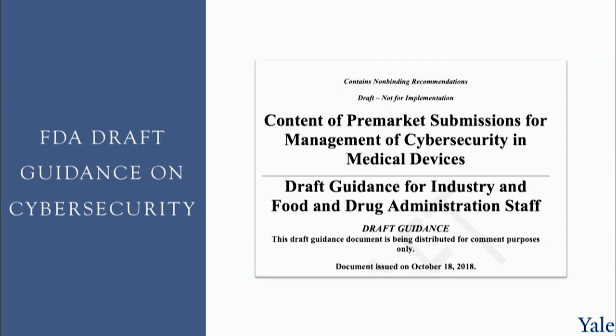So the FDA also has its guidance. It's a draft guidance, but don't let the word draft fool you. It still represents the thinking of the agency. And this is the content of pre-market submissions for management of cybersecurity in medical devices, which means, in plain English, this is what the FDA wants to see when you submit an application to allow your device to go to the market in terms of cybersecurity.